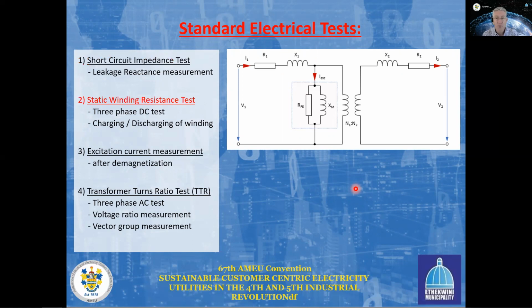Secondly, we do a static winding resistance measurement on a power transformer. This is typically done as a 3-phase DC test. Why 3-phase? Because it's quicker. It's important to make sure that the transformer is properly charged up with that DC, and you need to be careful because it can be dangerous if you disconnect any of the test leads, and you need to properly discharge that energy afterwards again. And then we basically characterize the resistances R1 and R2 as shown in my diagram here.